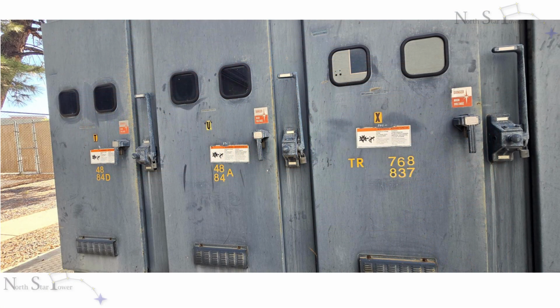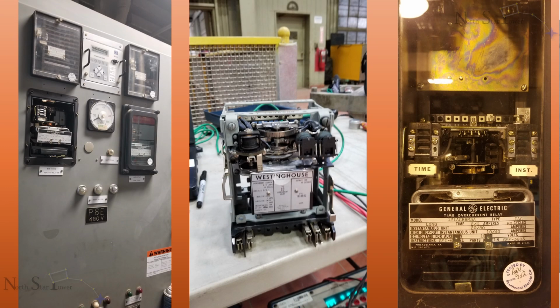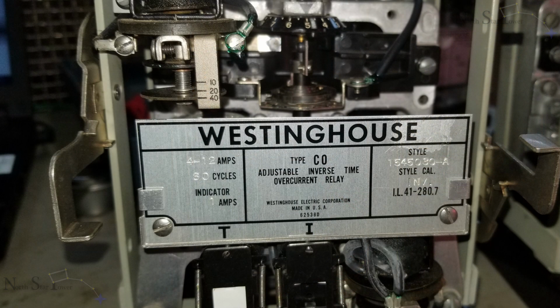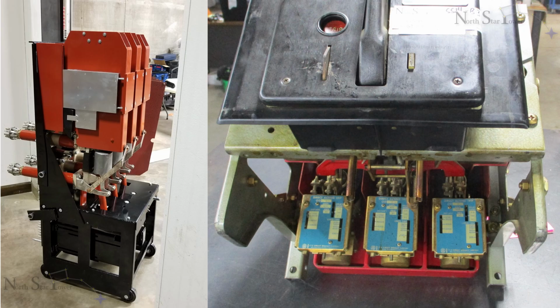Next, you should identify if equipment is obsolete. Common components that fail with age include breakers with dashpots, old mechanical relays, components containing asbestos, Bakelite, polychlorinated biphenyls or PCBs, cloth-insulated wiring, rotary converters, phenolic panels, knife switches, and exposed fuse disconnects. These should be replaced, rebuilt, or retrofitted.